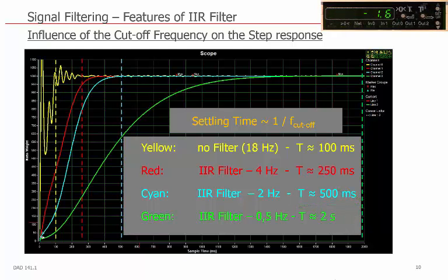Depending on the filter settings, the display of a non-automatic weighing instrument cannot show the dynamic of a falling load, but the load cells see this impulse and can be damaged if there are no overload stops mounted.